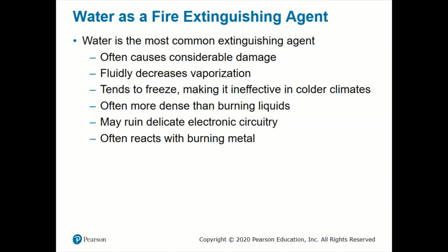Days like today, days like we've had in the past few days, cold temperatures can lead to freezing conditions, which again, if it freezes, we can't use it. And if it's super cold, it's going to be even harder to get it to vaporize. Because of its density, we can't use it for most burning liquids. It's not going to float on top, it's going to sink to the bottom. Again, if it sinks to the bottom, that actually just provides a vehicle for that burning fuel to go somewhere else.